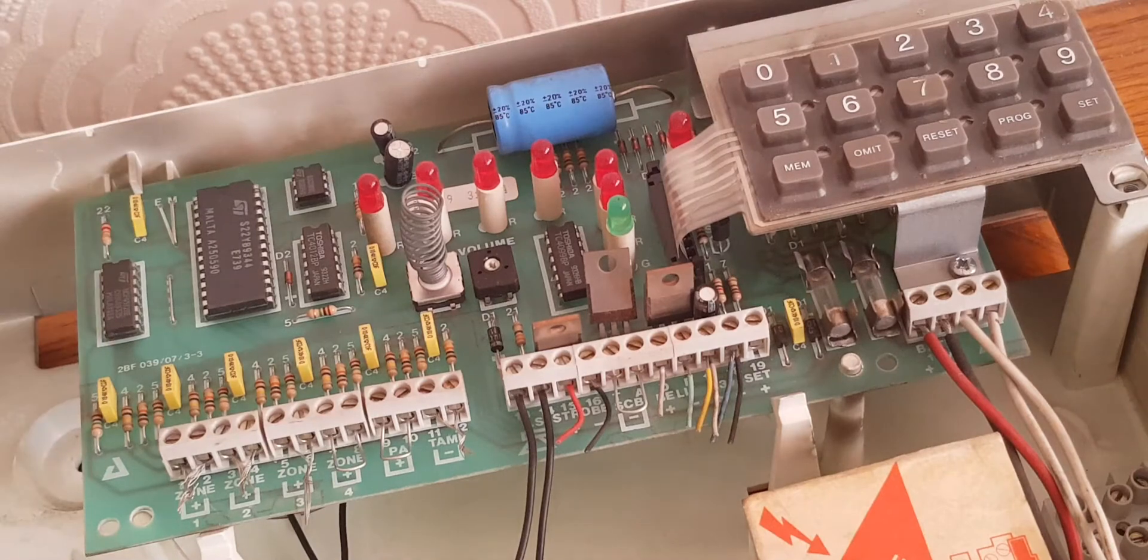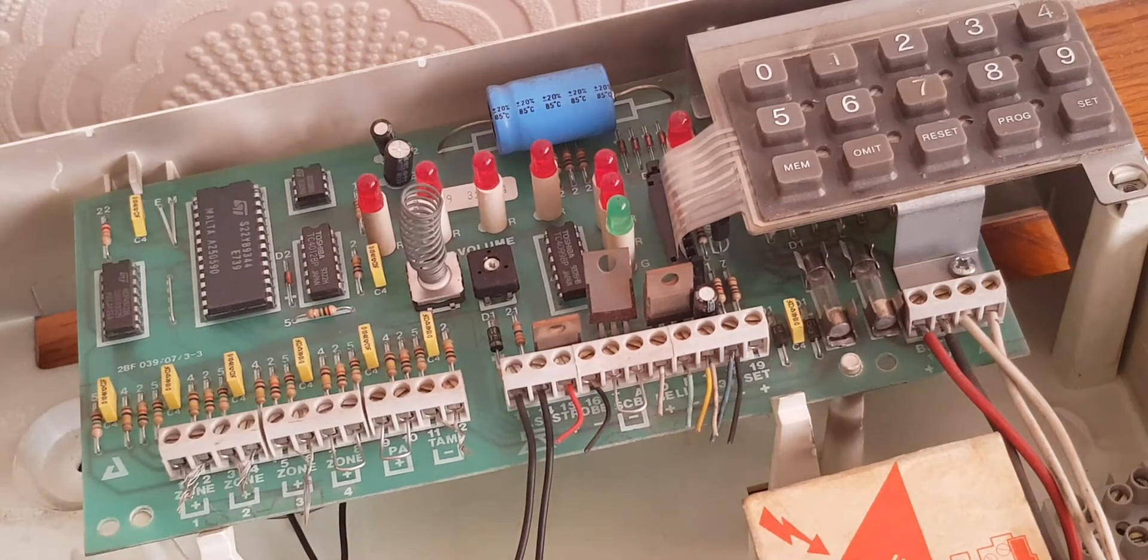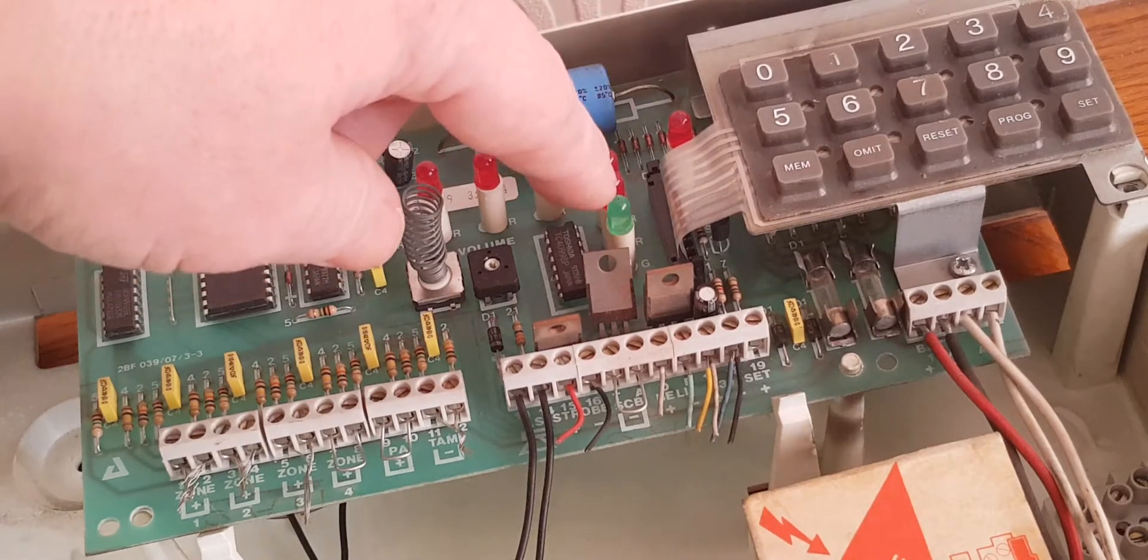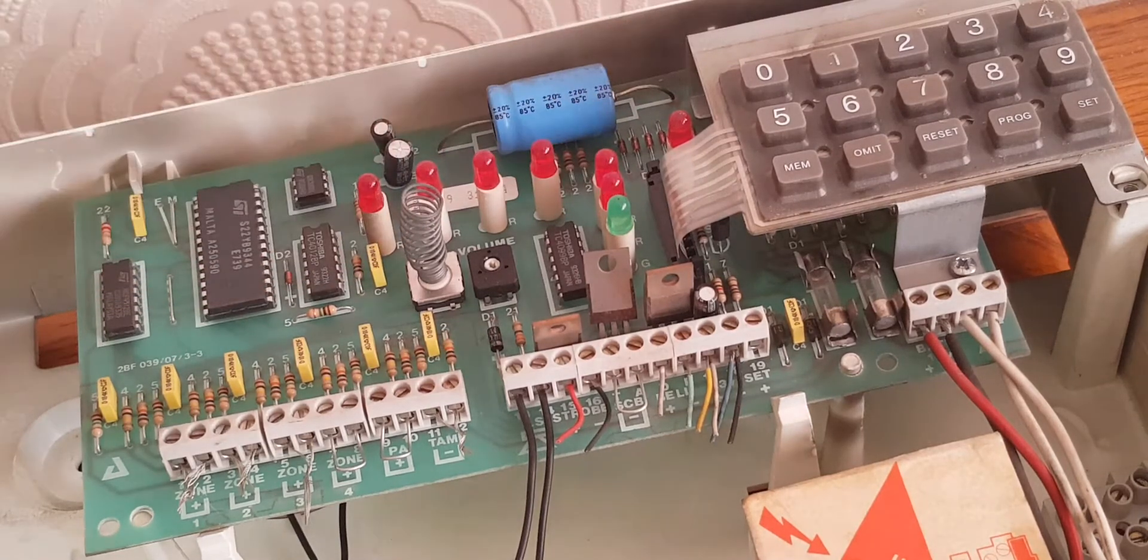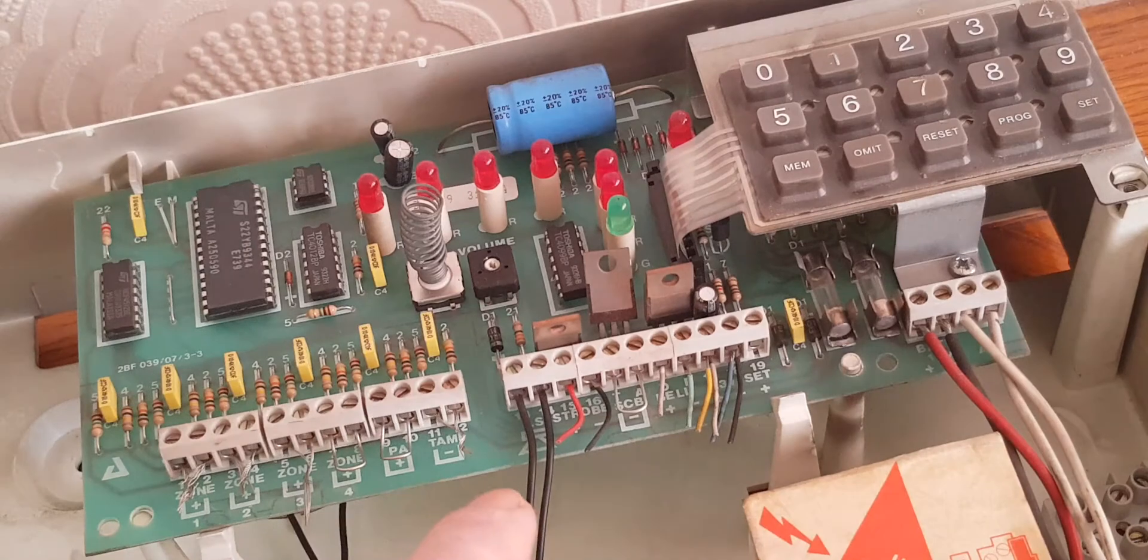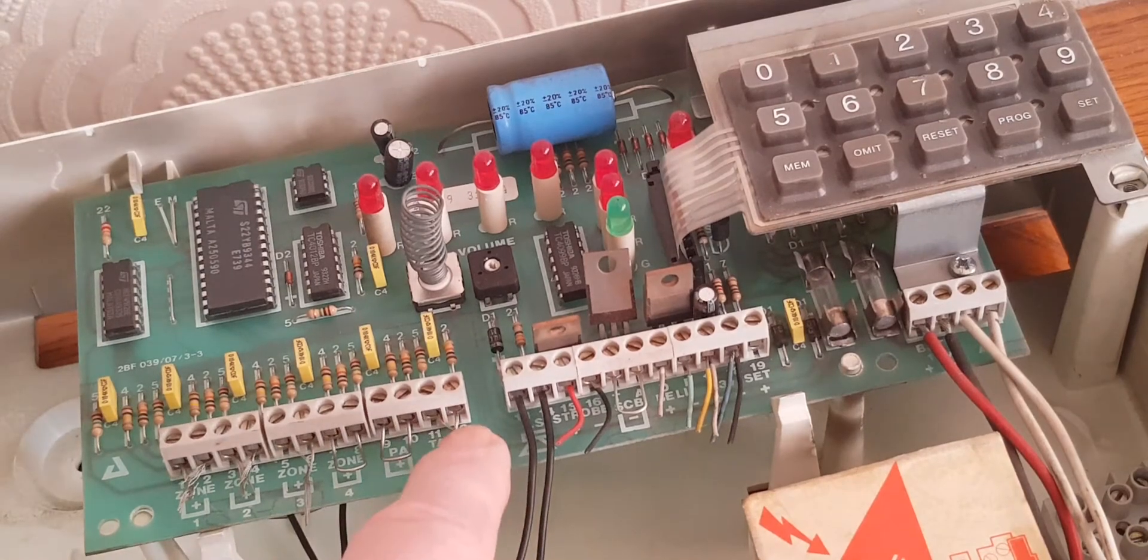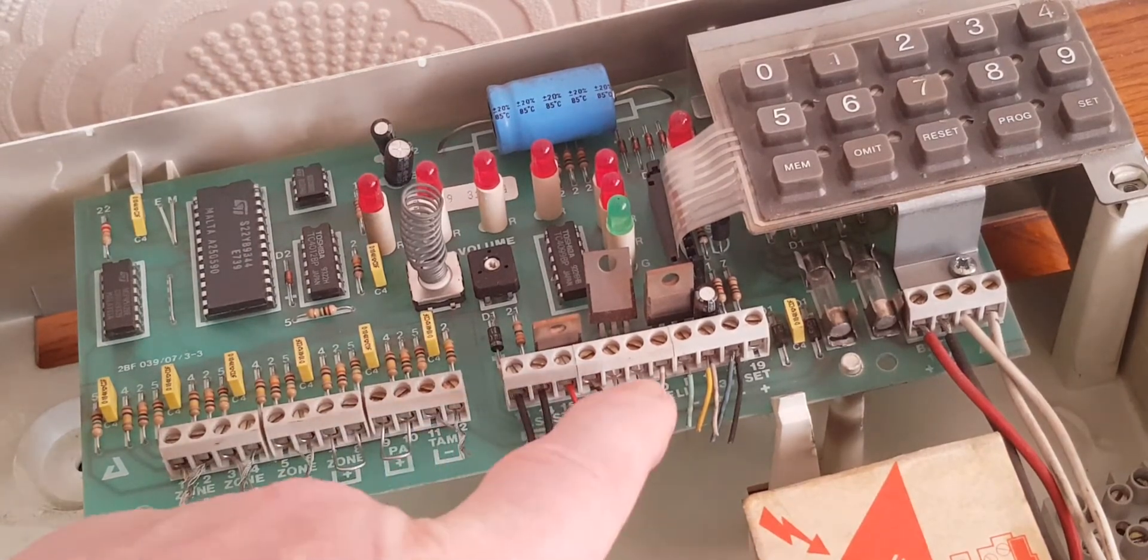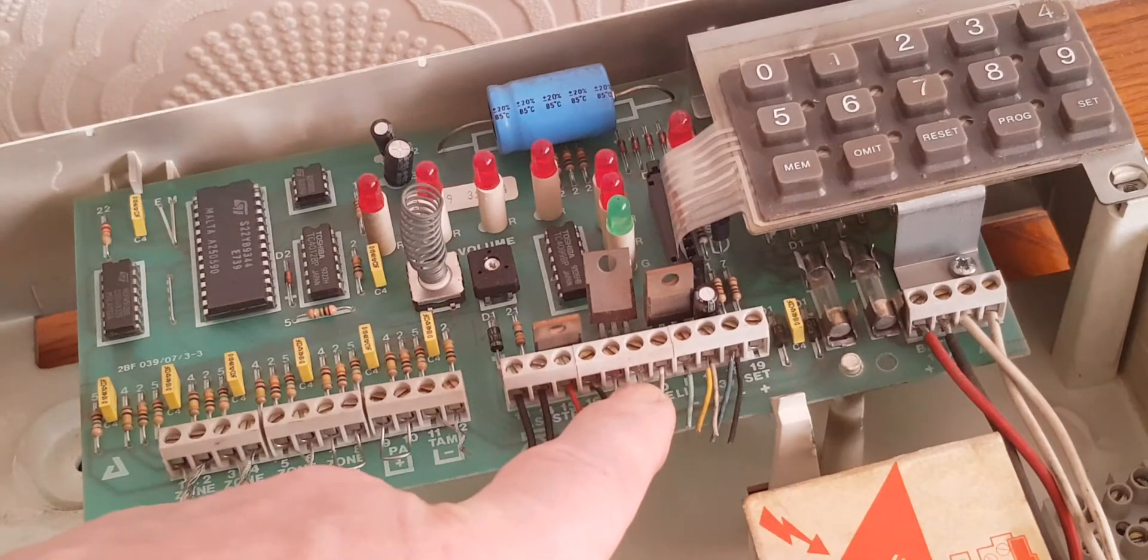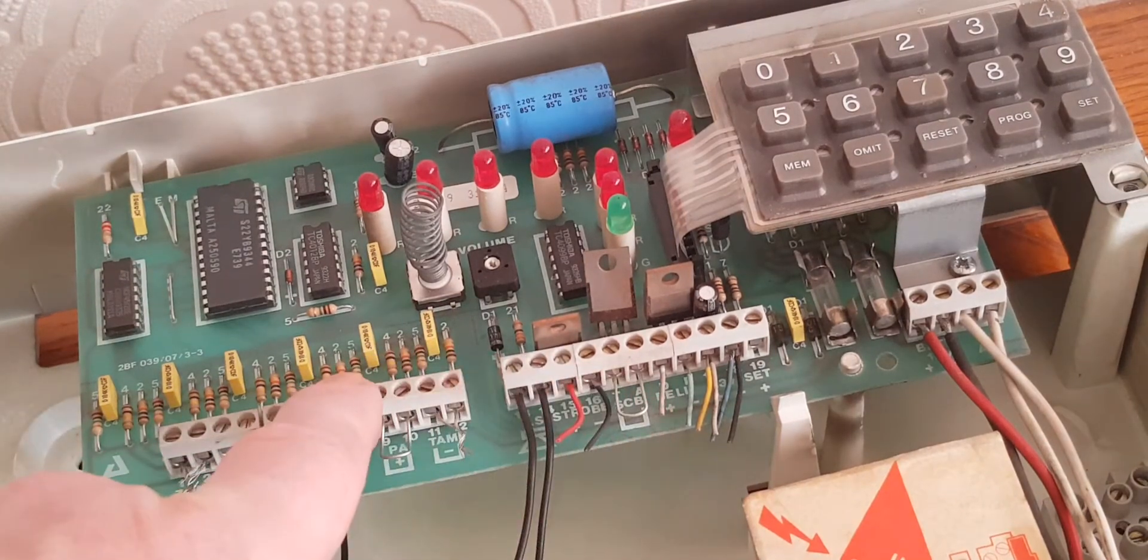I've done this today on this one, so it is working absolutely fine. But if you have a light on, say a tamper or something like that, or a PA, what you would need to do is go back and check your tamper. Check the PA and check your tamper on your bell, just to make sure that the cables are in firmly.